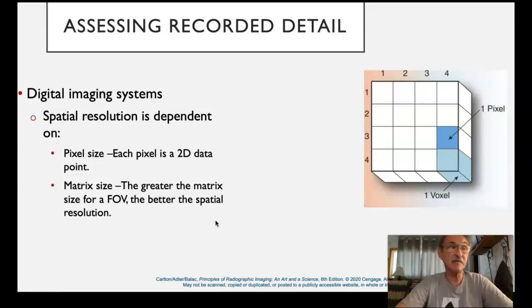When the X-ray beam comes down through the patient and interacts with the image receptor and the pixels, the pixel will record a certain value based on how much radiation it received. Each of these individual pixels keeps that particular reading, and then those are sequentially read out at the point when we do histogram analysis, at the point where the data is sent through the software program to process the image. Okay?